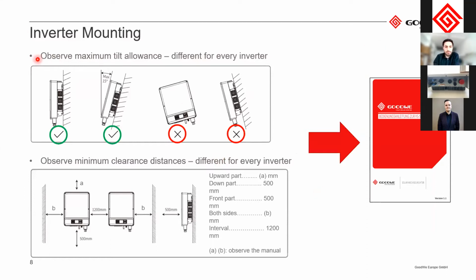All right. For the mounting of the inverter, a mounting plate is included in the package. However, there are a few things you need to observe when mounting it on a wall. First, please observe the maximum tilt allowance. Mainly they are supposed to be installed straight upwards. However, it is allowed to tilt them 15 degrees backwards, leaning towards the wall. But do not tilt them in any other way, because that will influence the cooling system too much, and then the inverter will not function properly.